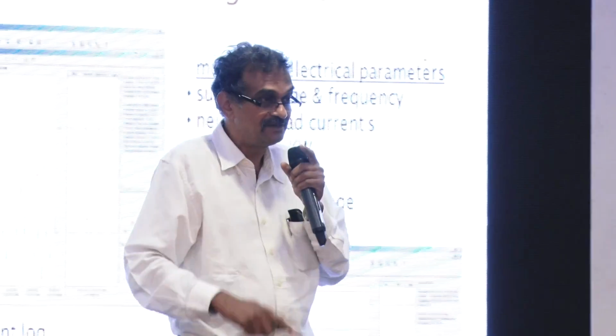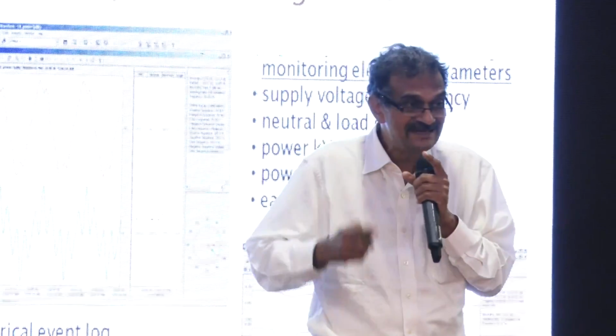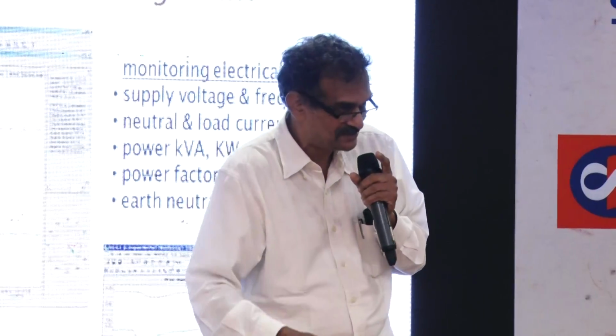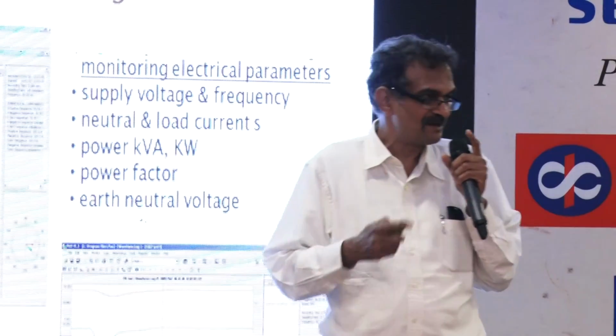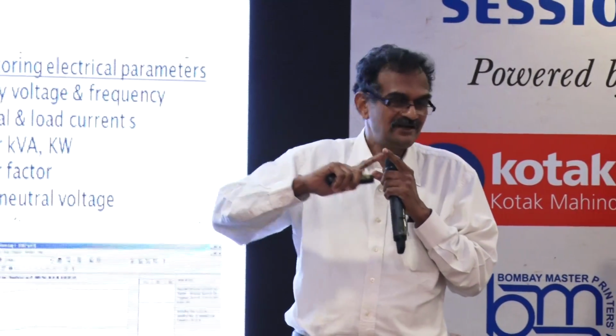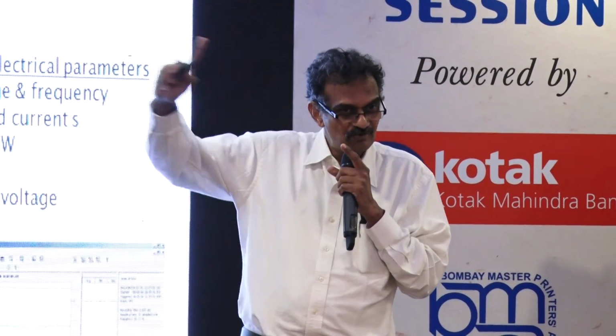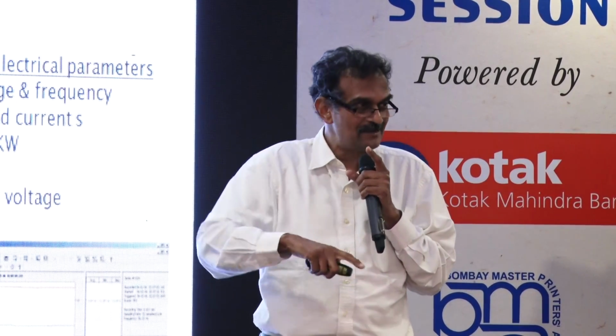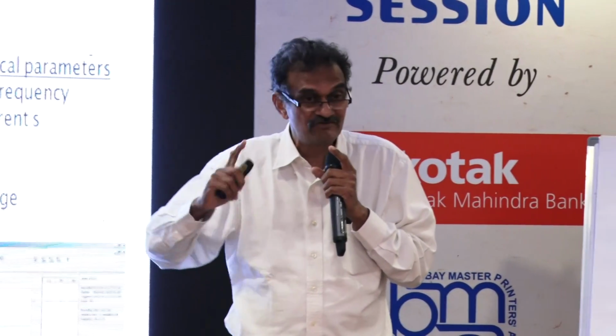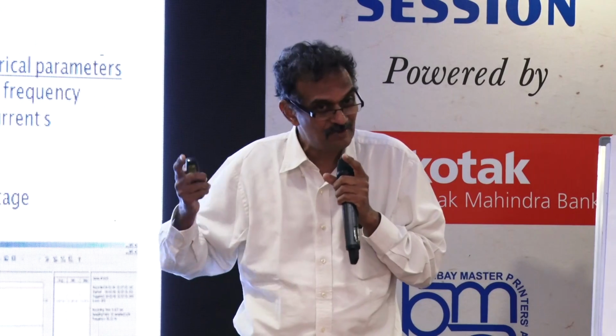But solutions are available. The next stage, they'll ask you to maintain harmonics less than 3%. Harmonics are the biggest culprits because your transformers get overheated, your switch gears get overheated. So when that stage comes, you need to plan in such a way that you're ready for deploying harmonic filters.